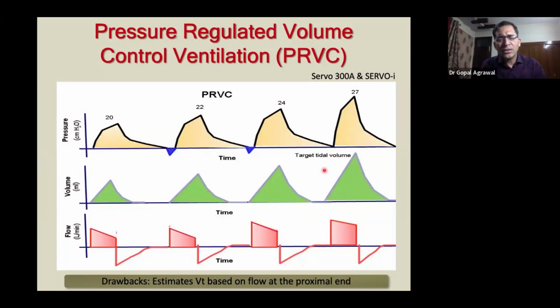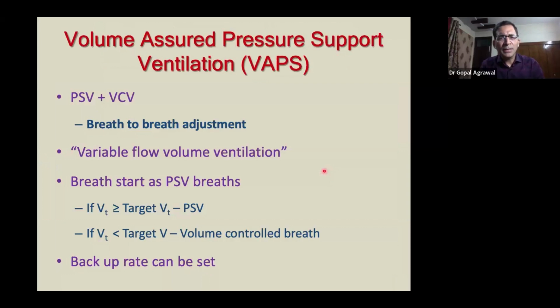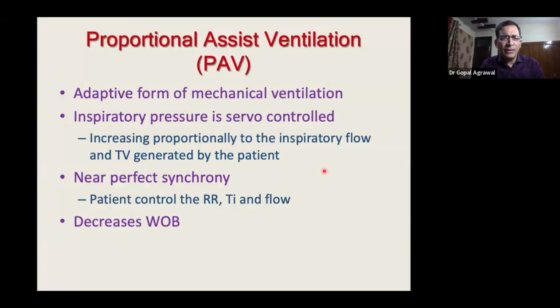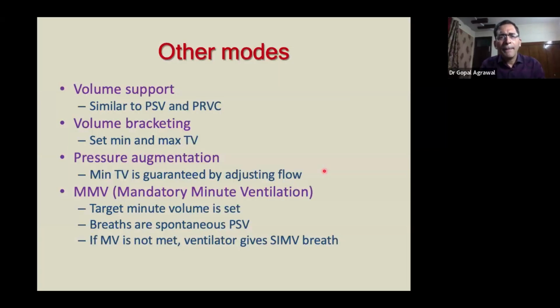The other disadvantage of Servo-i is that in PRVC mode, the tidal volume is detected at the proximal end, at the ventilator end, which is not good. The tidal volume should be measured at the patient end because the leak is properly detected that way. Something called VAPS and PAV, I'll not go into detail of that.